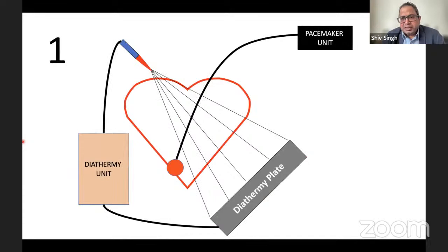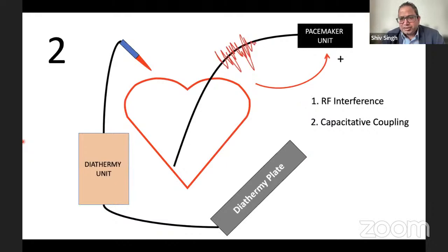The second thing is radio frequency interference. Diathermy machines work at very high frequencies. This produces radio frequency waves, which can cause radio frequency interference and capacitive coupling, and again can cause interference in the monitoring. You see it all the time: whenever the surgeon uses the diathermy, your ECG goes haywire, sometimes the pulse oximeter too. That's because of radio frequency interference. It's got nothing to do with leakage of current through the wires. With capacitive coupling, you have two conducting electrodes separated by air, and that can cause interference. So there can be resetting of the pacemaker unit. That will be discussed in more detail when I discuss the pacemaker.